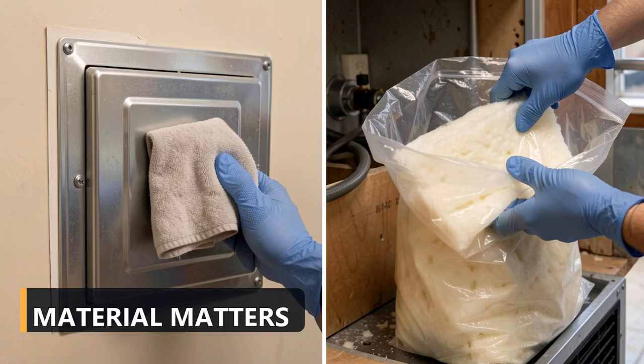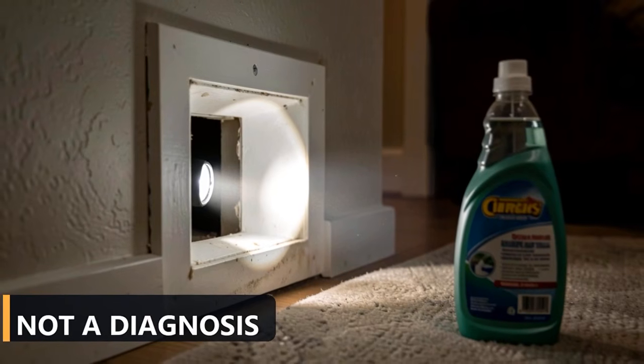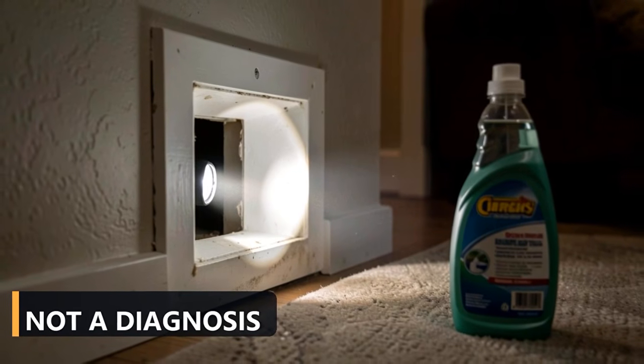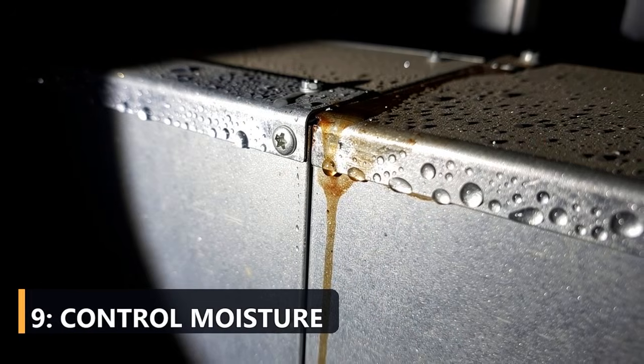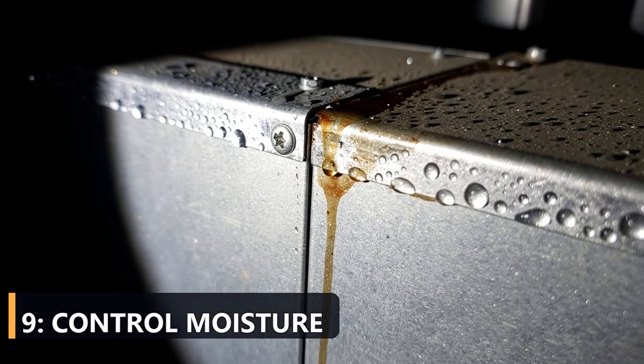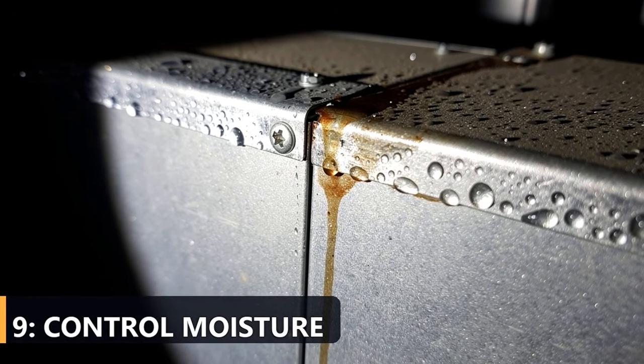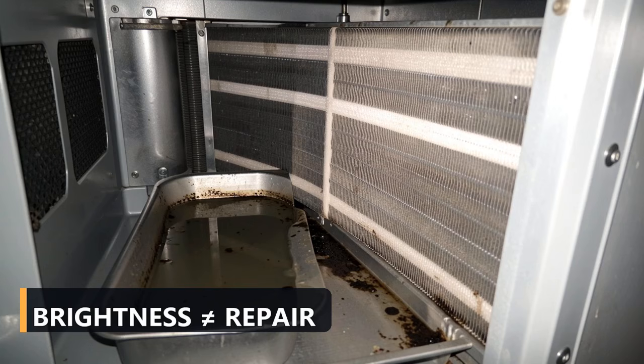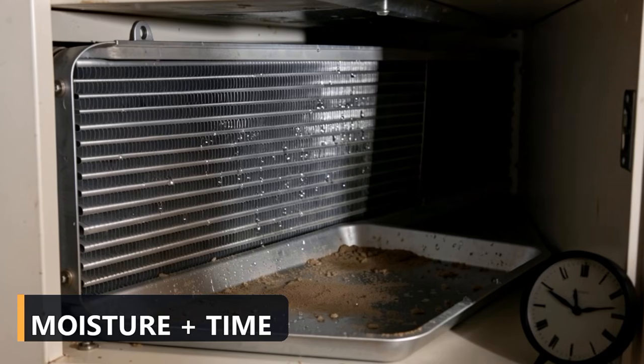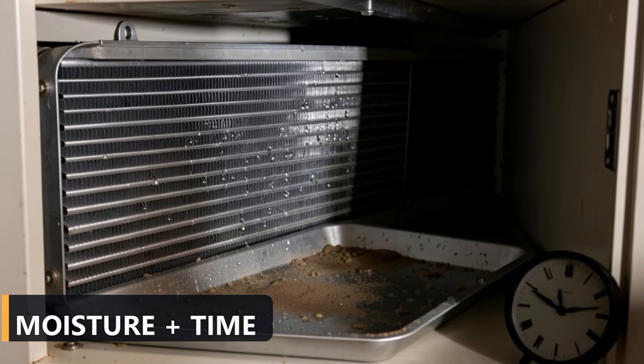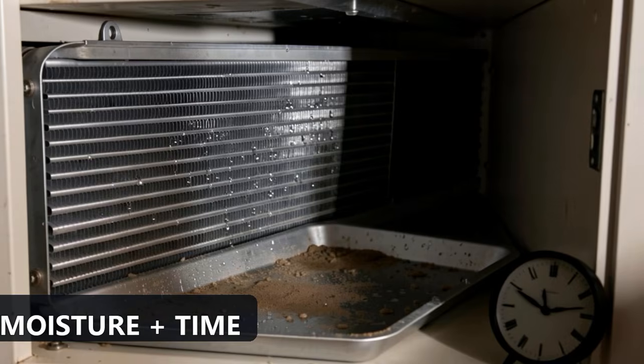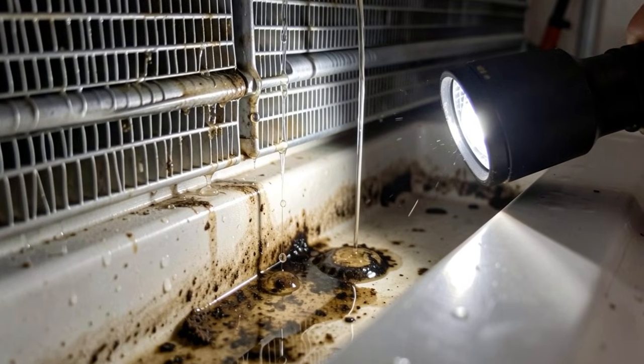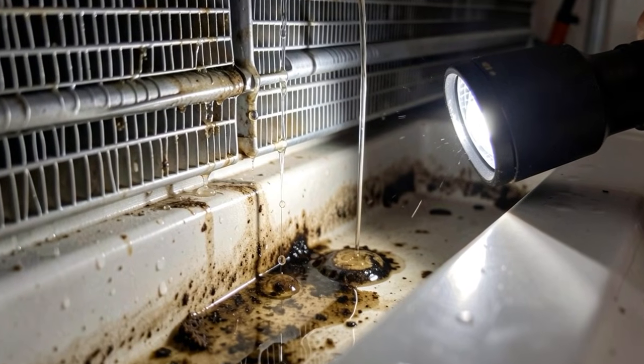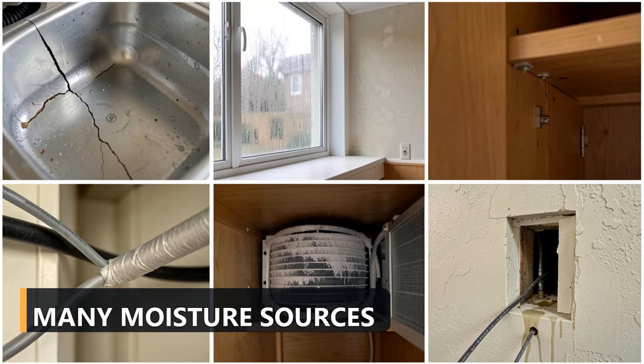Number 9. If the moisture problem remains, the smell and growth will return. This is the secret that separates a 1-minute transformation from a repair. Mold and odor inside an HVAC system are not created by a shortage of peroxide. They are created by moisture, nutrients, temperature, and time. The moisture may come from normal condensation combined with poor drainage, a clogged line, a cracked pan, high indoor humidity, air leakage around the cabinet, missing insulation, a frozen coil, or water entering from somewhere outside the system.